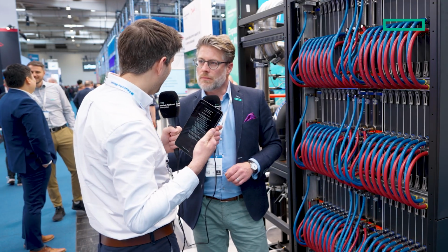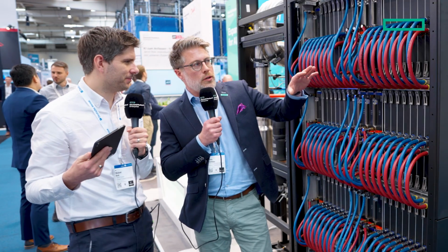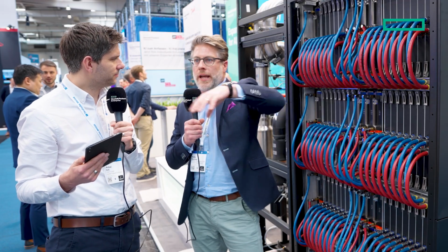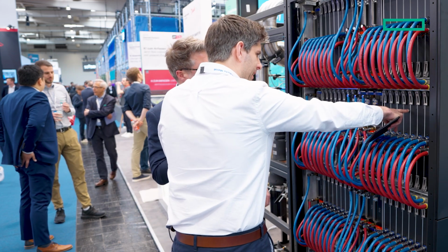I'm assuming if these were fans, we wouldn't be standing here, it'd be quite loud. No - and you would have to sort this capacity into at least 8 racks to cool them, because it looks very dense, so closely tucked into each other. Yeah, that's what I mean by 400 kilowatts - that's currently the highest density in industry, and HPE is the only one offering pure liquid cooling at that density.